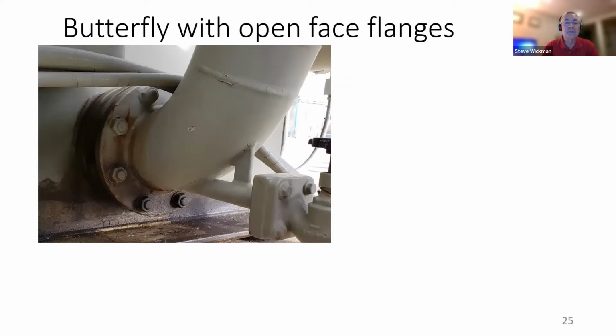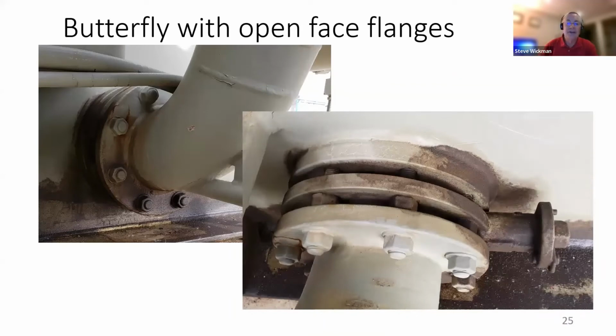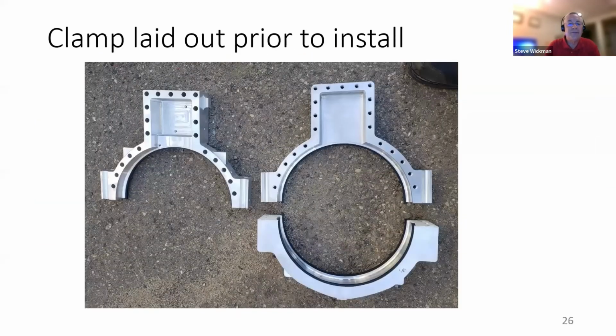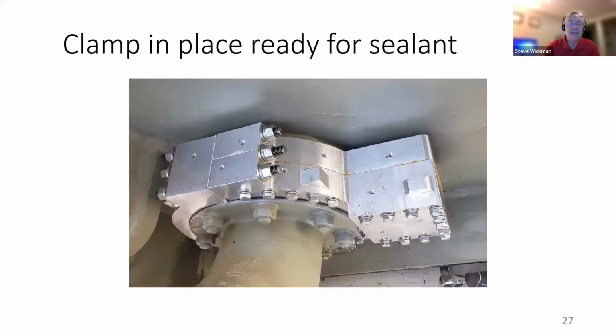Here's another butterfly valve or flapper valve with an open face flange that you can't drill and inject because of the open face configuration there. But in this case, we designed and fabricated a big three-part clamp to go around that flange that you can see in the photograph here and prep for going into place. You can see a couple of the holes that have been drilled here for the sealant compound to get injected into that cavity. Once that clamp is in place, there's your clamp in place, and you can see those holes for the sealant to get pumped into to effectively contain those leaks.